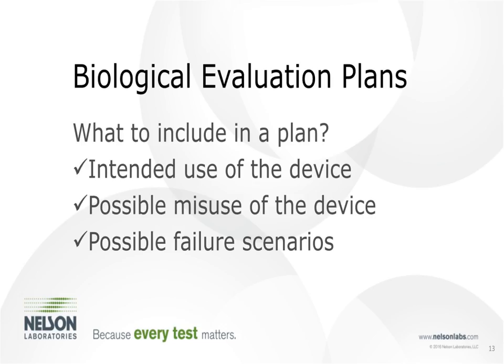So when we're looking at biological evaluation plans, and remember, these are really just plans that evaluate the risk of these devices to the patient, to be able to spell out where your gaps are and identify how to evaluate those gaps. So what should be included in these plans? Well, the first thing is we still need to talk about the device. We still need to evaluate its intended use, how long it's in contact with the patient, where it's in contact with the patient, what population it is exposed to, is there a special population, neonates or infants, that we may have more risk for.